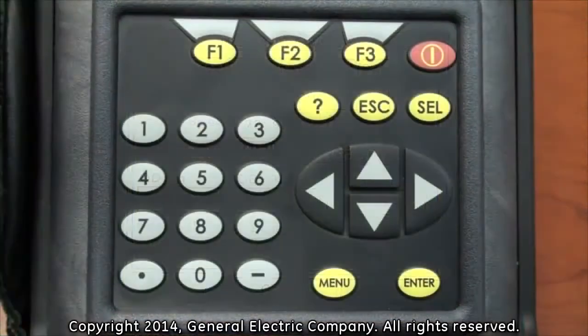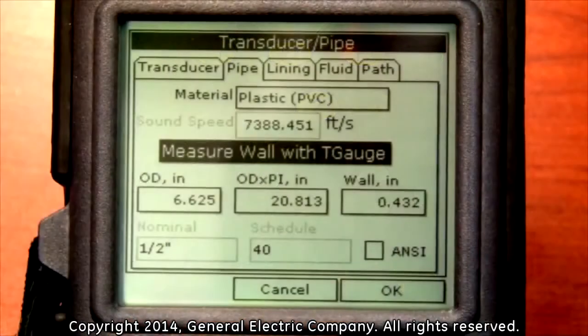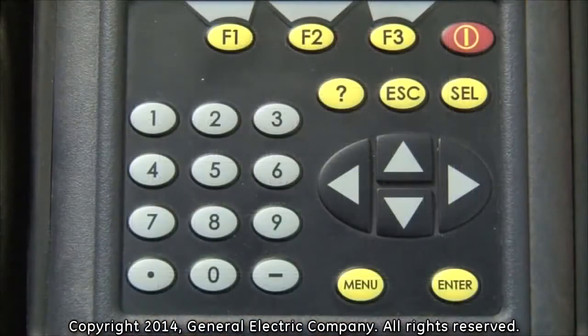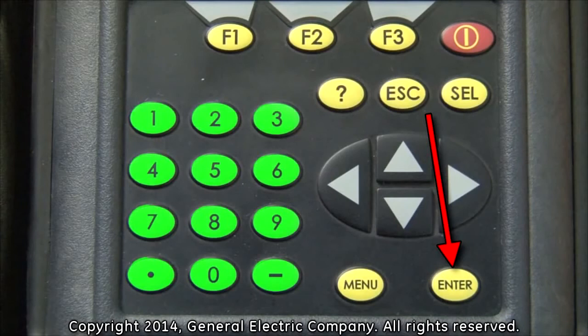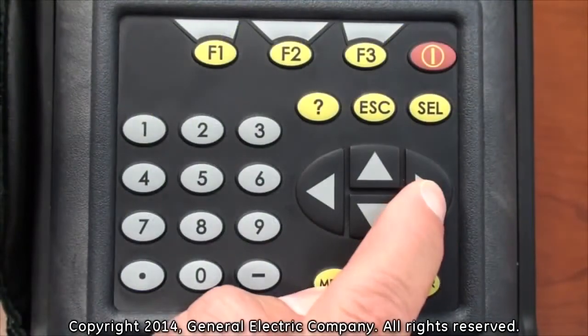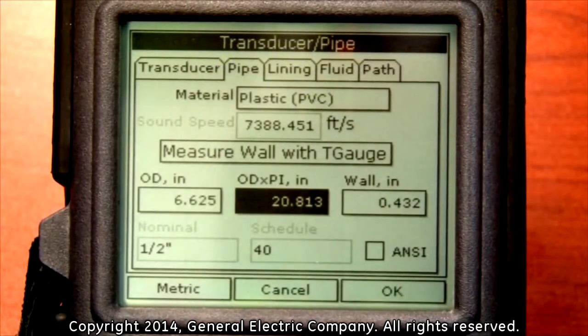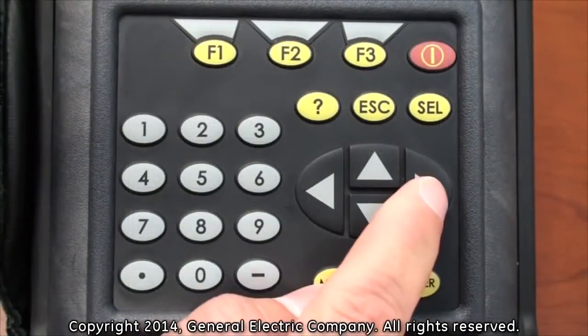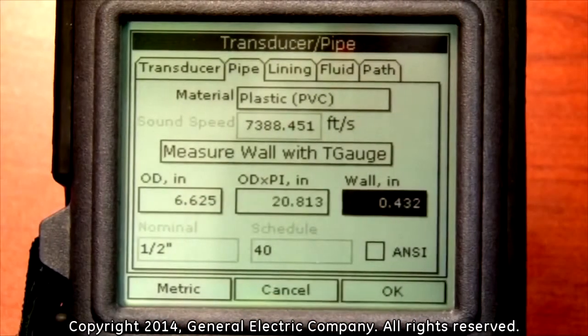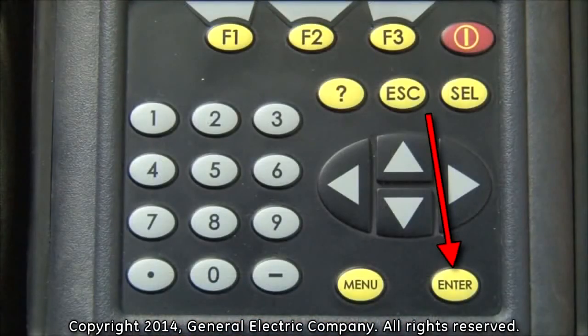Once your wall thickness is measured, use the down arrow key to highlight the outer diameter input field. After measuring the outer diameter of the pipe, press the Enter button and use the number keys on the keypad to input the outer diameter of the pipe. Once the diameter is entered, press the Enter button again. You do not have to input any value in the OD times pi field, as it will automatically be calculated after putting in your wall thickness. Use the right arrow key to move over to the wall thickness input field and press Enter. Input the value of the wall thickness that is measured from the wall thickness gauge by using the number keys on the keypad. Press the Enter button once you have input the wall thickness value.